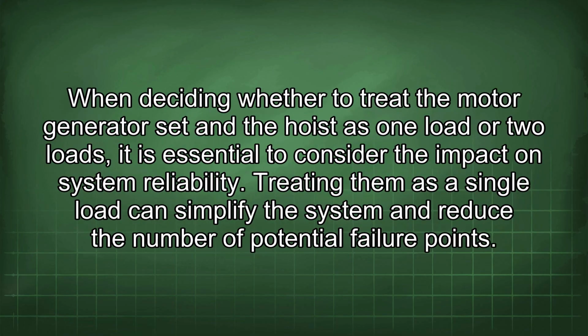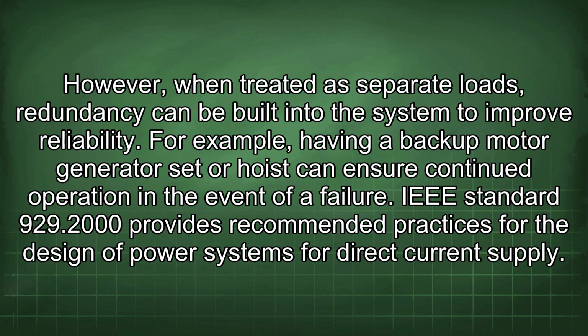When deciding whether to treat the motor generator set and the hoist as one load or two loads, it is essential to consider the impact on system reliability. Treating them as a single load can simplify the system and reduce the number of potential failure points. However, when treated as separate loads, redundancy can be built into the system to improve reliability. For example, having a backup motor generator set or hoist can ensure continued operation in the event of a failure.